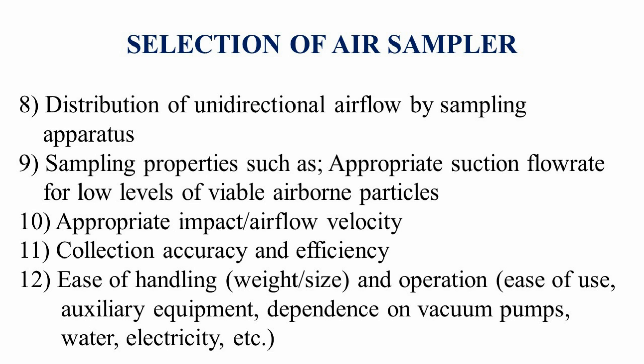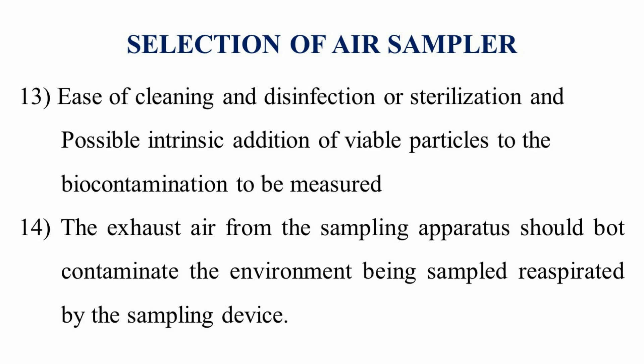Twelfth consideration is ease of handling and operation. The sampler must be of low weight and small size, and should be easy to operate. Thirteenth is ease of cleaning, disinfection or sterilization, and the possible intrinsic addition of viable particles to the biocontamination being measured. Fourteenth is that the exhaust air from the sampling apparatus should not contaminate the environment being sampled or be aspirated by the sampling device.